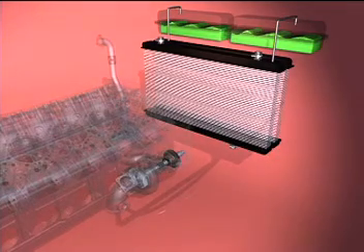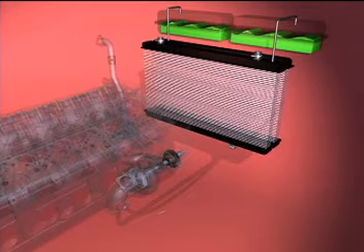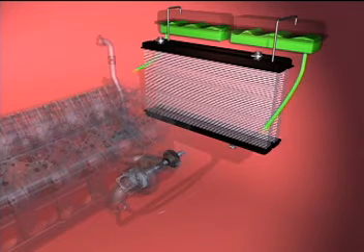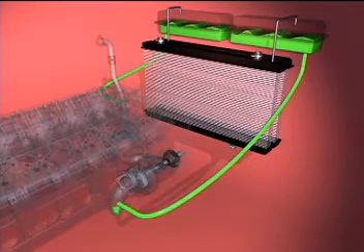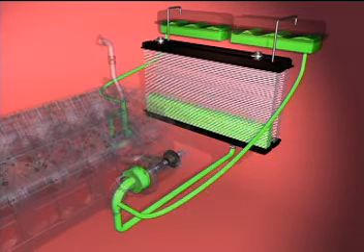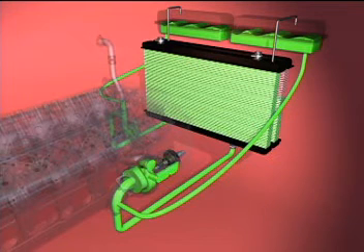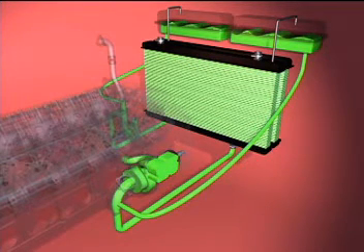The HT loop and the LTA loop in the cooling system are filled through the respective fill lines. These lines carry coolant from the makeup tanks to their respective pump inlets. This purges air from the system by filling the engine from the bottom up. Air is purged from the cooling system through vent lines that connect to the top of the aftercooler.